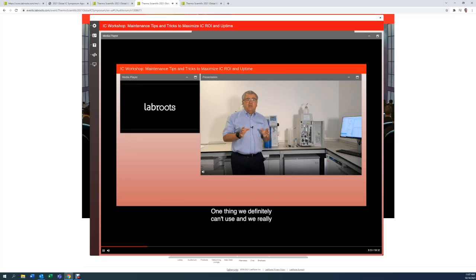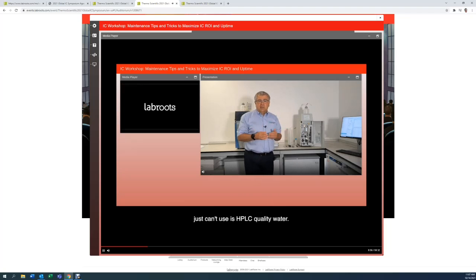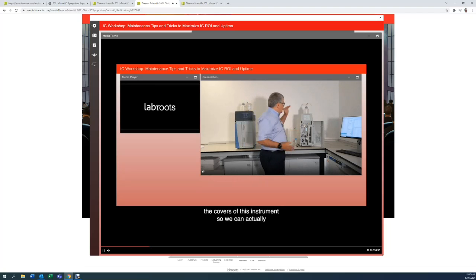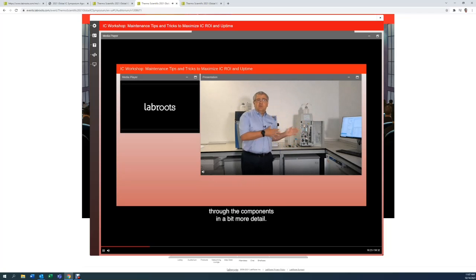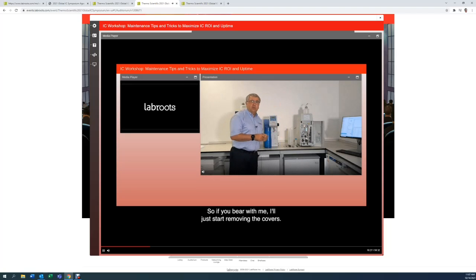One thing we definitely can't use, and we really just can't use this, is HPLC quality water. HPLC quality water, by definition, is designed for reverse phase HPLC. They don't really take any of the ions out of there. They take out any of the UV absorbing species, but it can be quite heavy in terms of ions or ionic contamination. So what I'm going to do now is I'm going to remove the covers of this instrument so we can actually see some of the components, and we can take you through the components in a bit more detail. So if you bear with me, I'll just start removing the covers.